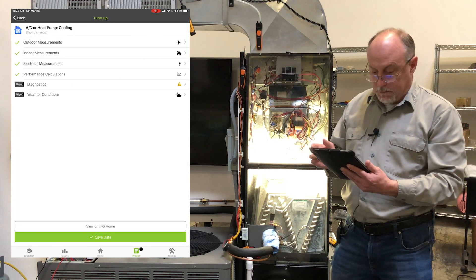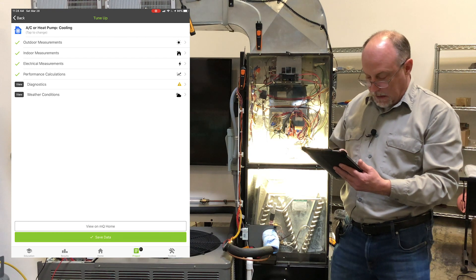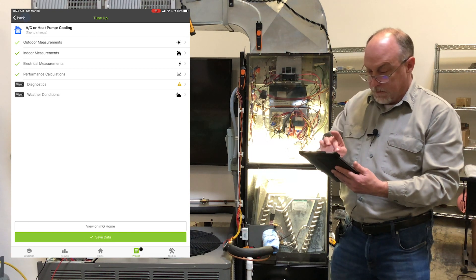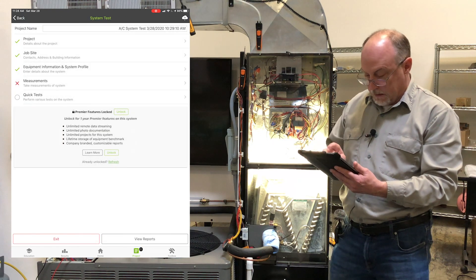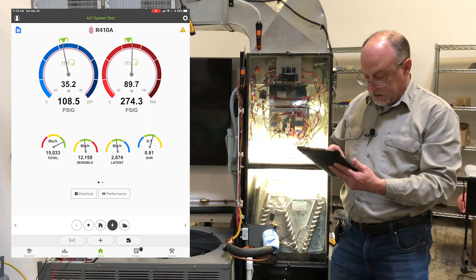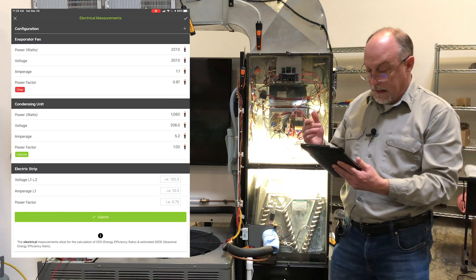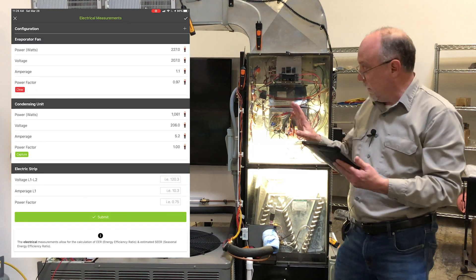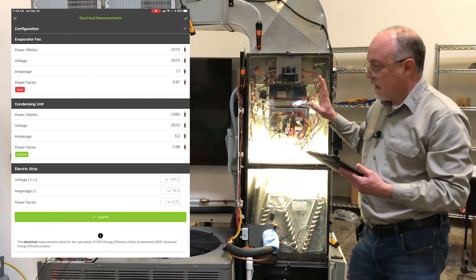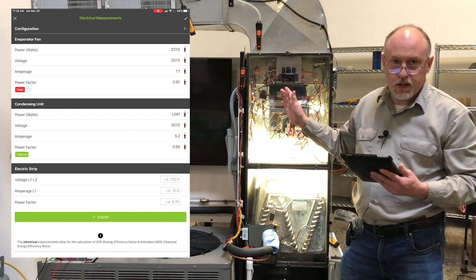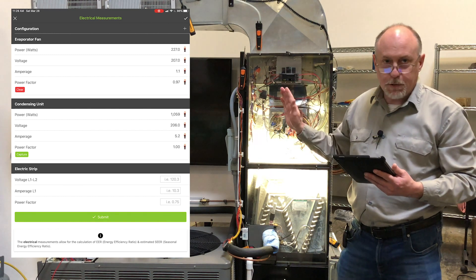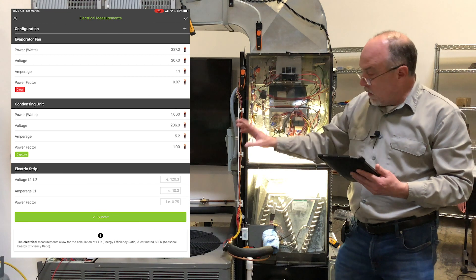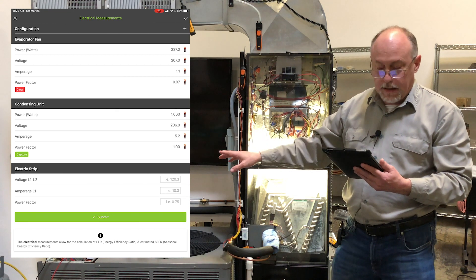Now, I just haven't submitted my measurements. I'll show you this just for interest here. If I hit the back screen here in home, you'll see in electrical here, I do have the air handler data captured. And I always recommend you just go ahead, as soon as you start the system up, capture the air handler data.